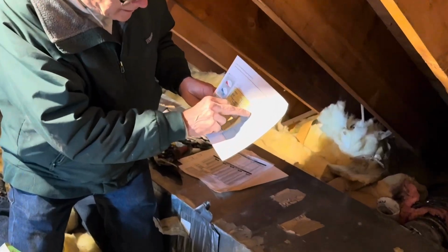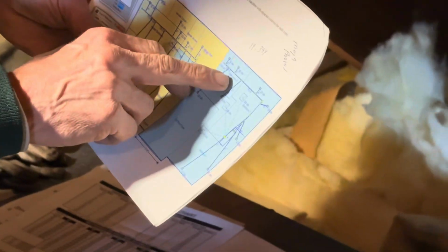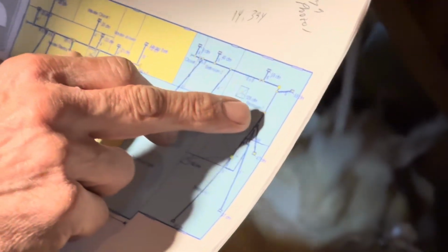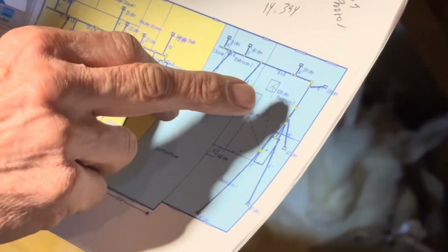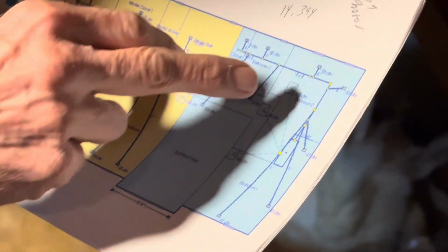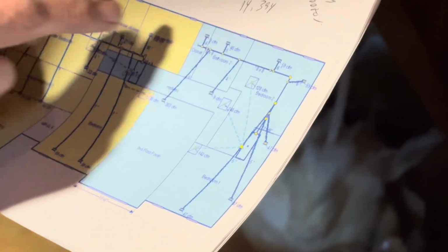We would need in the closet 4 cubic feet a minute of air, hardly anything, right? We would need in the bathroom 40, so now we have 44. In this room, we need 120. So 120, 160, 164, just to feed this part of the duct system.